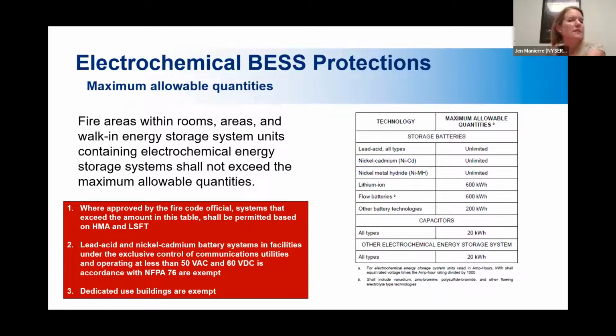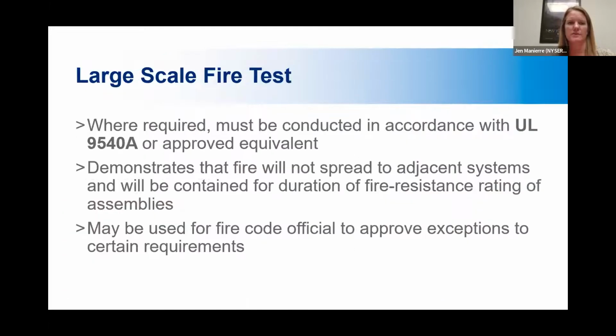And here, maximum allowable quantities. This is just another excerpt from the code. It shows that there's a few types up top that have unlimited quantities that you can put in one given space. For lithium ion, the maximum is 600 kilowatt hours. You'll notice that is the same threshold that we used to separate our tier 1 and tier 2 systems in the model law. If anyone wants to go above 600 kilowatt hours, that's where you're triggering the requirements for this large scale fire test and the hazard mitigation analysis.